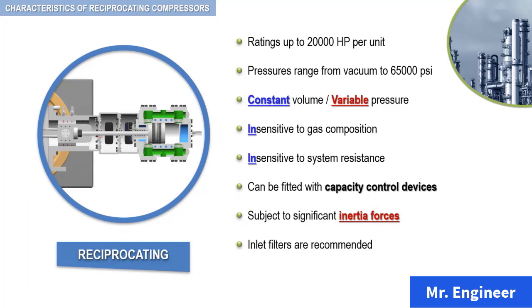Finally, one last characteristic is that reciprocating compressors deliver a pulsating flow of gas. This is sometimes a disadvantage, but pulsation dampeners can usually eliminate the problem. The pulsation control of reciprocating compressors and the design of dampeners will be covered in detail further ahead.